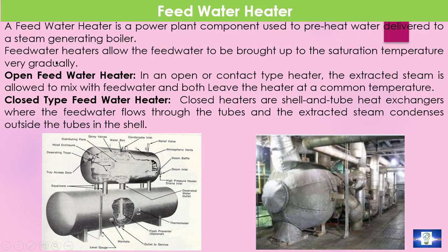In the Rankine cycle of a steam power plant, feed water heaters allow the feed water to be brought up to the saturation temperature very gradually. This minimizes the inevitable irreversibilities associated with the heat transfer to the working fluid, meaning water. The feed water heaters are open and closed type heat exchangers.